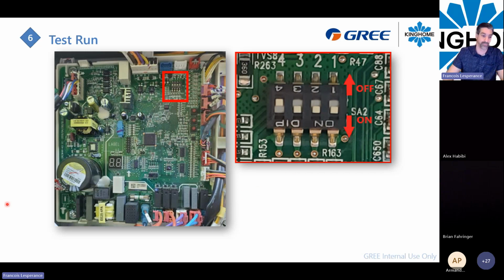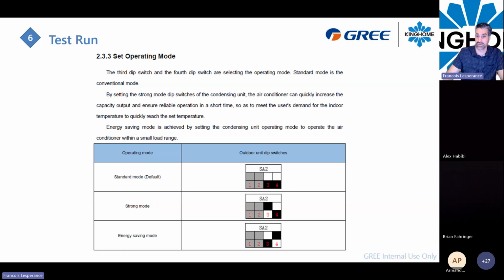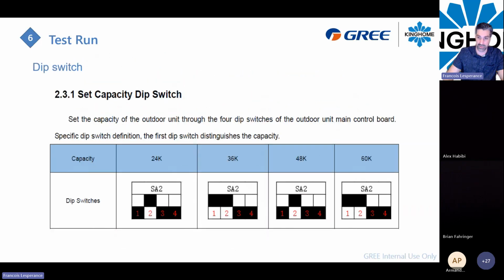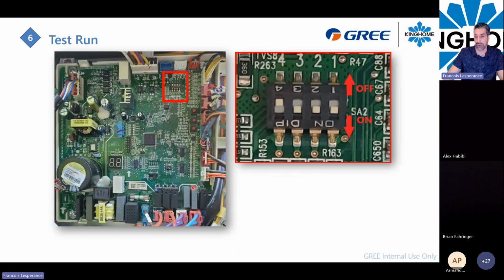to make sure you have a good adjustment. If I go back a couple of slides to give you that example, this is a 3-ton unit. By default it's supposed to be off, off, on, off, off. If I go 1, 2, 3, 4, so on, off, off. On this slide I have on right here, it's a 3-ton unit. So that's my capacity switch right here. It's on, so I have a 3-ton unit. If I put it off, I will have a 2-ton unit.